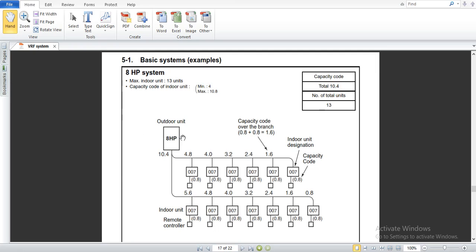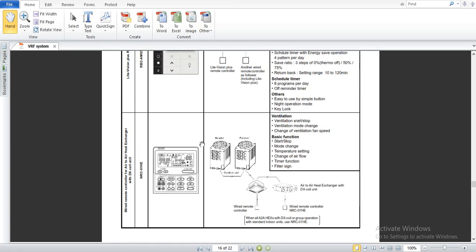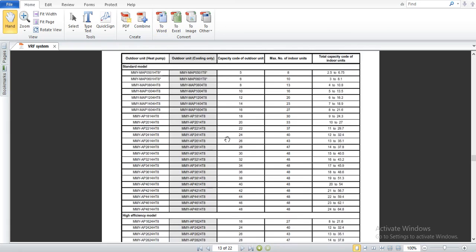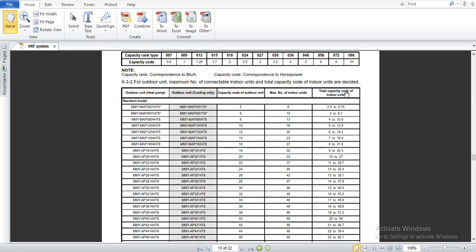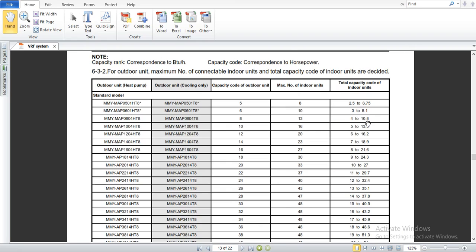Now we select the outdoor unit. We have 8 horsepower here. The total capacity code of the indoor units is 10.4, which lies between 4 and 10.8 — that's okay. The maximum number of connectable indoor units is sufficient, and we have 13 in our project. So the corresponding outdoor unit is 8 HP. If we need only cooling, we select the cooling only model. If we need both heating and cooling, we select the heat pump model. This is how we have selected the 8 horsepower system.